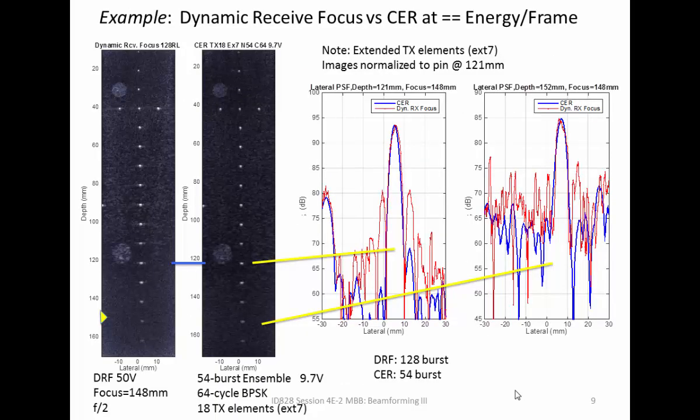To give an example, comparing to dynamic receive focus with 128 scan lines: the coded excitation uses a sparse 18-element transmit aperture, 54 transmissions, 64-cycle-long codes, at nine volts versus 50 volts for the dynamic focus algorithm focused at 148mm. We see pretty much identical main lobe response, but five to eight dB better clutter rejection than the dynamic focus. Going closer in where dynamic receive is out of focus, we're still focusing very well with the synthetic transmit aperture operating on the coded excitation impulse response estimates.